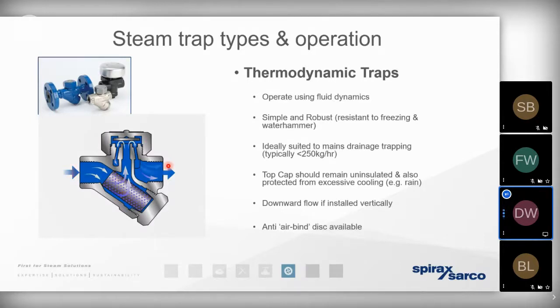So there are benefits and there are disadvantages of this type of trap. The benefits, it's very small, it's robust, it's compact, it's easy to install. Providing we've observed the directional flow, we can install it in any plane. If it is exposed to freezing condensate, it isn't going to cause any damage. Once the steam system is switched on and pressurized again, that condensate will thaw out and the trap will operate as it did previously without any damage.